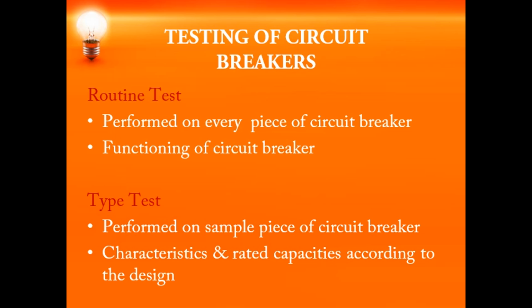It's a broad classification. Okay, and all the routine tests and the type tests will be performed according to the Indian standard codes, that is IS codes, or the International Electrotechnical Commission, that is IEC, or British Standard codes, that is BS codes. So now we will be looking into how the circuit breaker is tested for breaking capacity, making capacity, short time current, rating capacity. When we come to the testing category, we have direct testing techniques and indirect testing techniques. We will see in the coming slides.